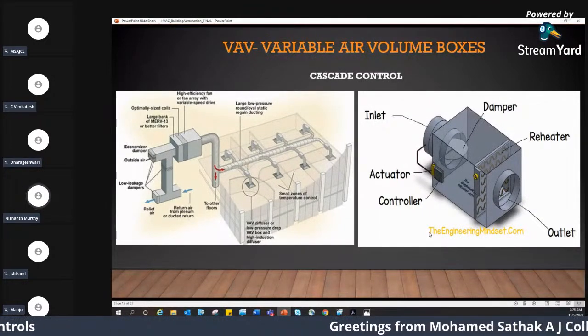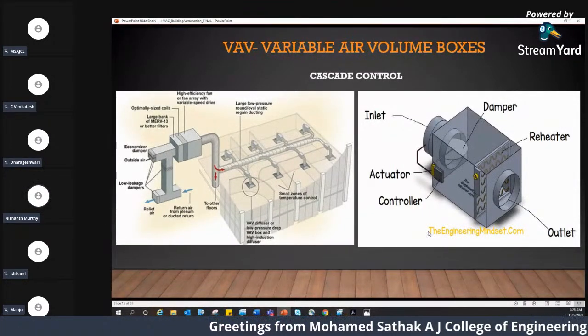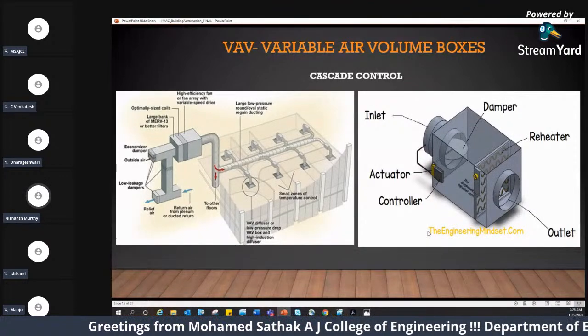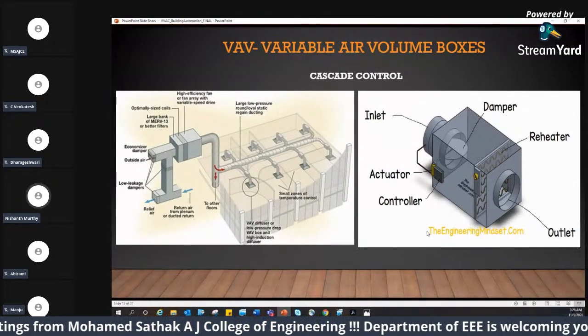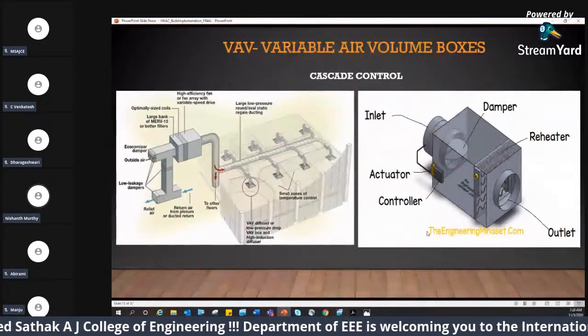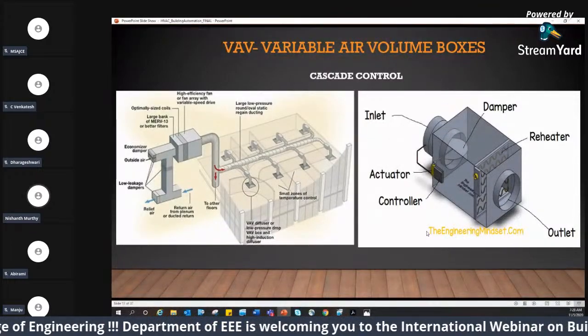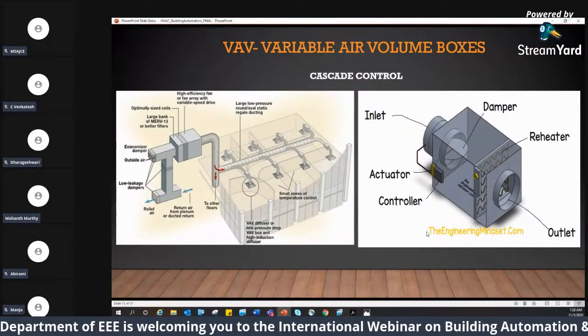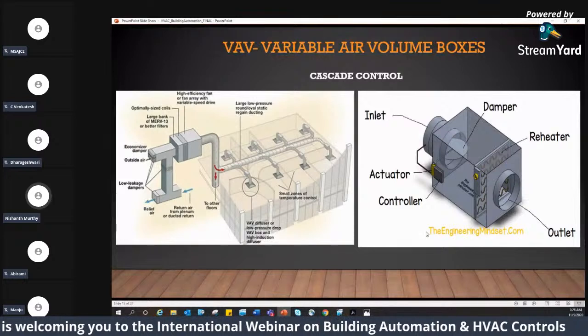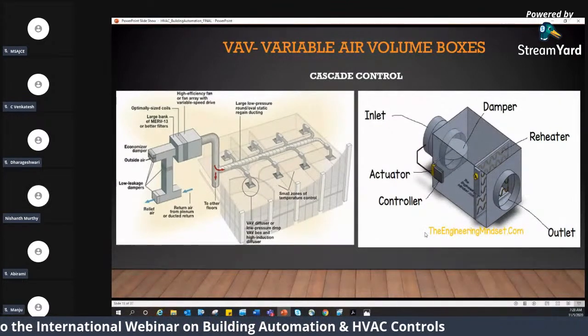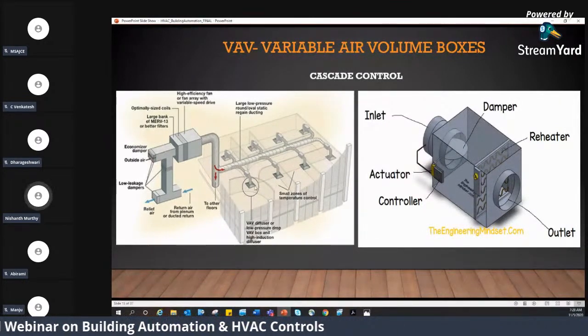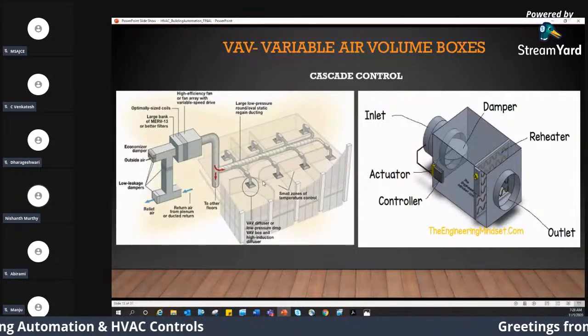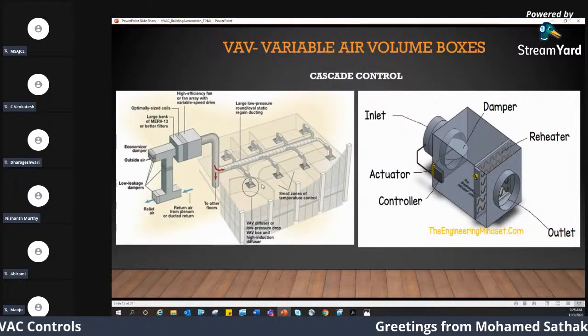So it has two controls in it. That's the concept of VAV, variable air volume. To brush up again, your AHU supplies air to the VAV. Your VAV will control the temperature in the room by controlling the damper position, which in turn controls your airflow. All right. The picture is self-explanatory. We have inlet, outlet, damper, and actuator. The actuator is a controlling equipment for your damper and valve, which I'll explain in the upcoming slides.